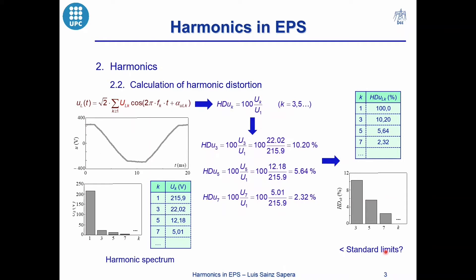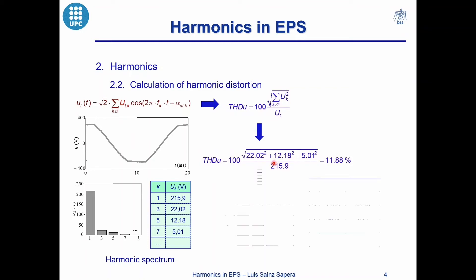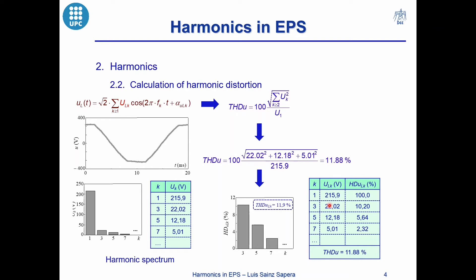After verifying the level of distortion of the voltage waveform, I will determine the total harmonic distortion. For this I calculate the root mean square value of the harmonics and divide this result by the root mean square value of the fundamental waveform. I can show these results together with the table of individual harmonic distortions and the bar plot, and compare these results with the limits of the standards.